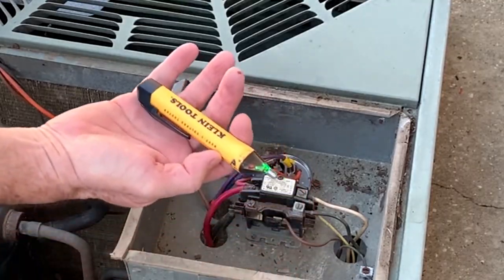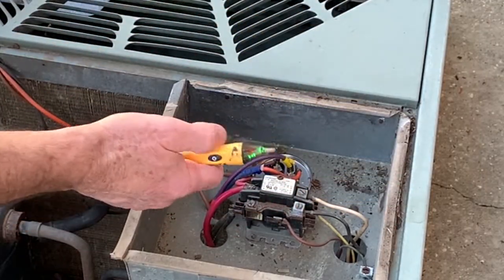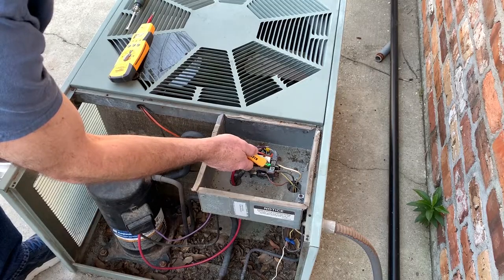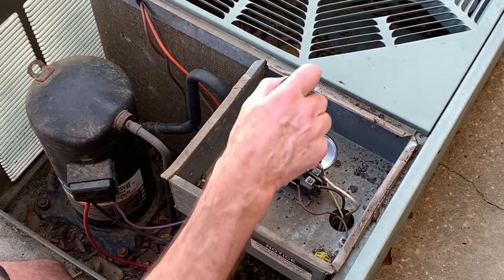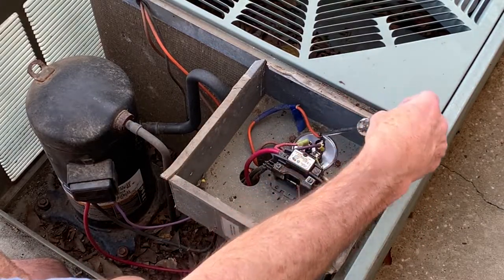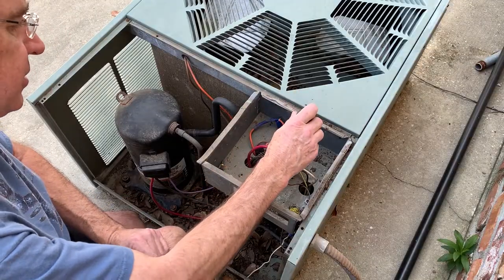This is a Klein non-contact voltage tester. You always want to make sure these are working before you use them — see the green light is on. I touch the two power legs coming in and I'm not getting any voltage. Even though we have all the power turned off, there's still energy stored in the capacitor. So before we do anything with this capacitor, you want to make sure we short all the wires out — short all the terminals to each other. It's a little bit harder to do in here, so I'm going to pull the screws out and then do it.